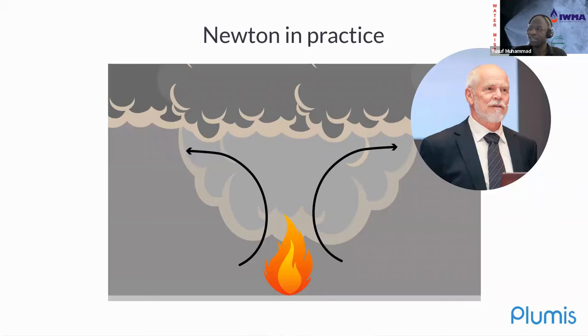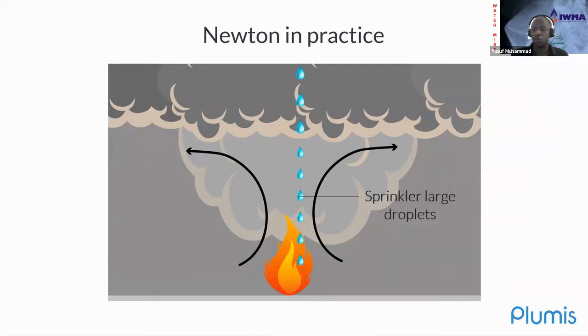Now, just to explain this, traditional sprinkler systems use Newton's law, gravity. They use large droplets, and they're attempting to wet all of the surfaces in the room, not only to get water into the base of the fire, so these large droplets going against the updraft that the fire creates, but also wet all of the areas around the fire so that the fire has nowhere to grow to. All of those materials are completely soaked.